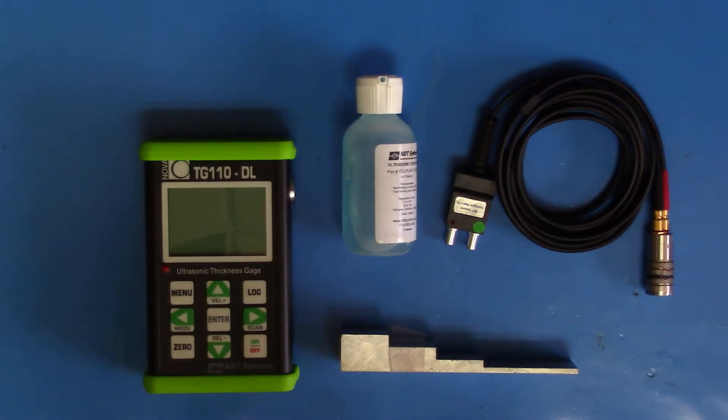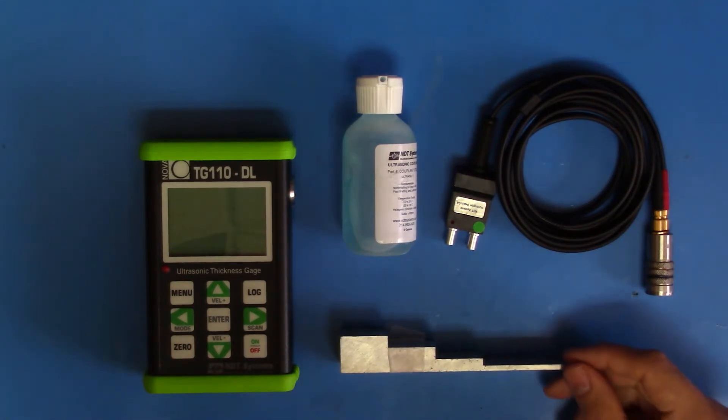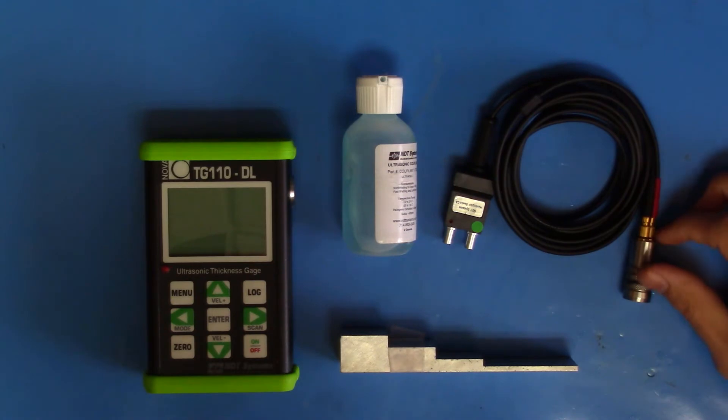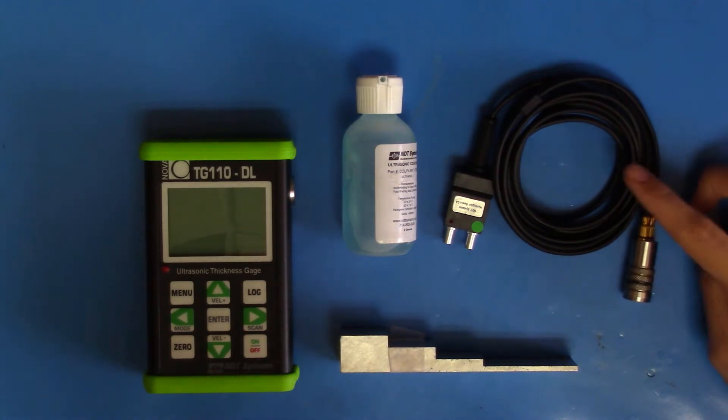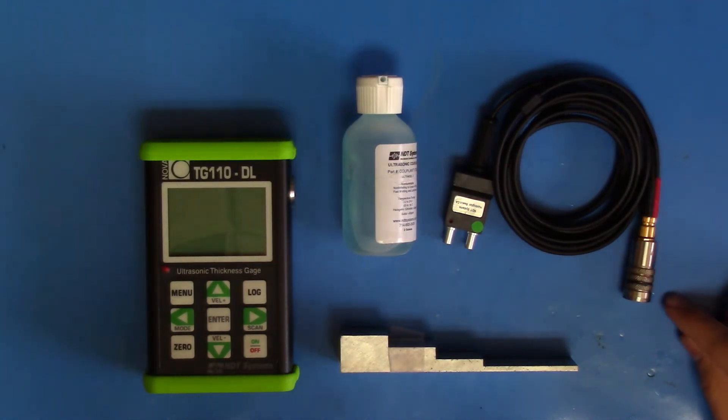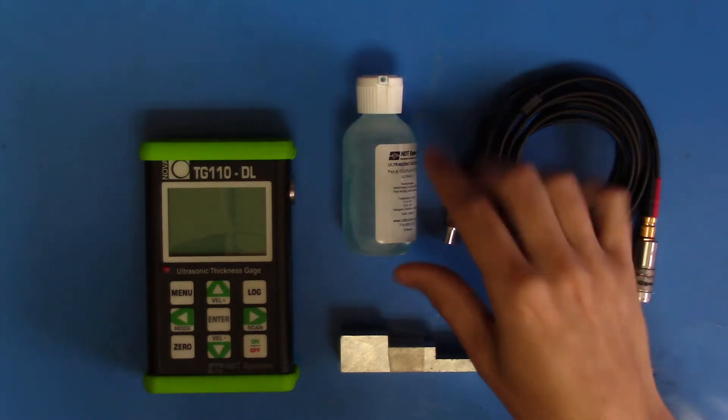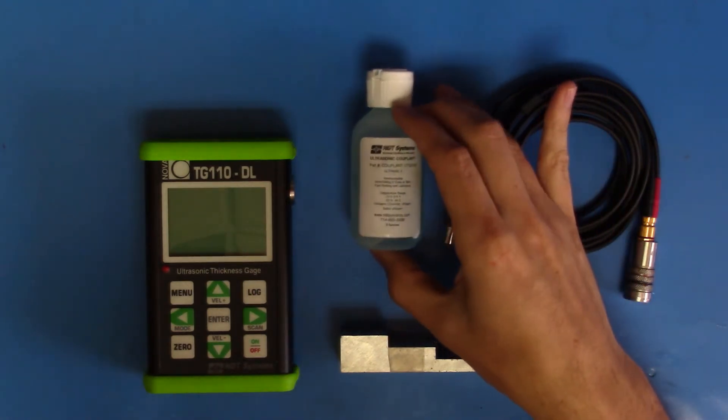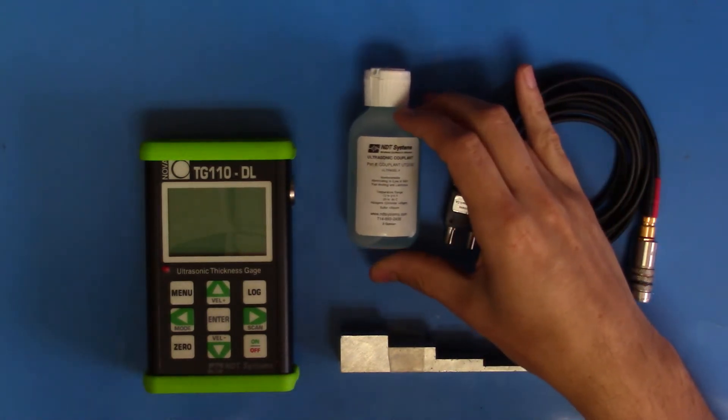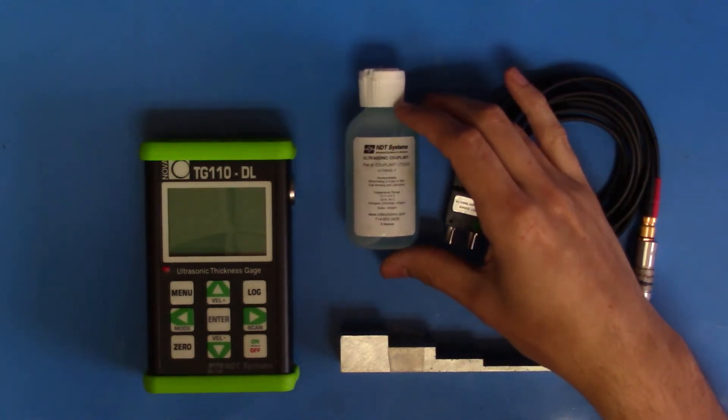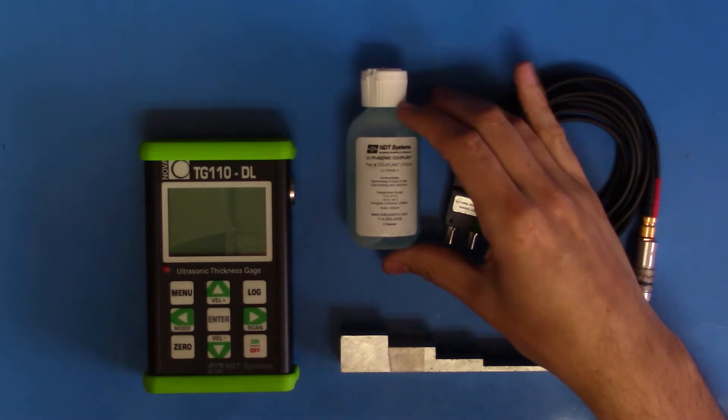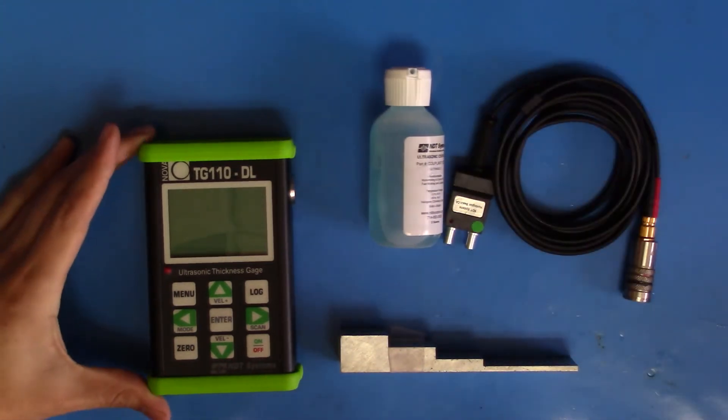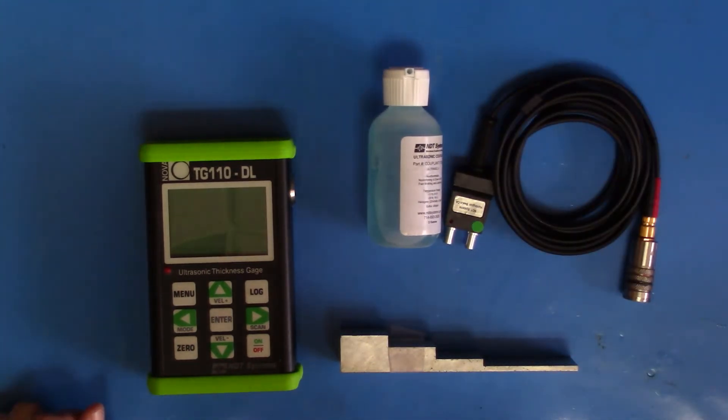In order to do this, we'll need a standardized step block, a ThruPaint-capable probe along with its cable. This is a TG560P. We'll need a couplant of some sort. This is a glycerin-based ultrasonic gel, and we have our gauge, of course.